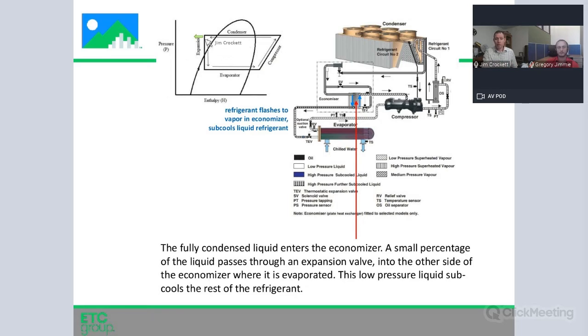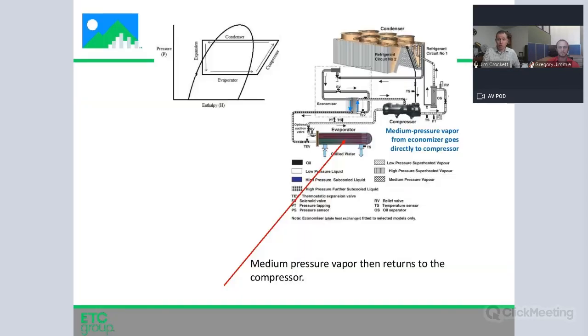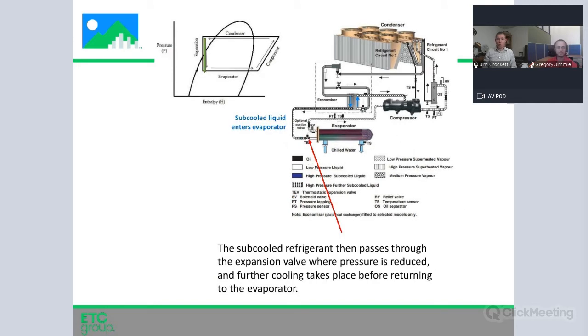And what that does, if we look at our P&H diagram, is it slides us further to the left. It slides us further into subcooling. The reason we do that is because we don't want any of the liquid to accidentally evaporate before it hits the evaporator. So there's a small subcooler there. The medium pressure vapor that we flashed for the economizer goes back to the compressor, and the subcooled refrigerant makes its way back to the evaporator, and that's where the cycle ends.